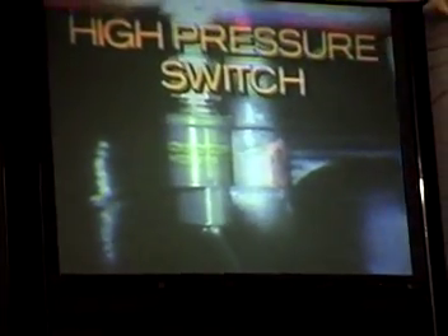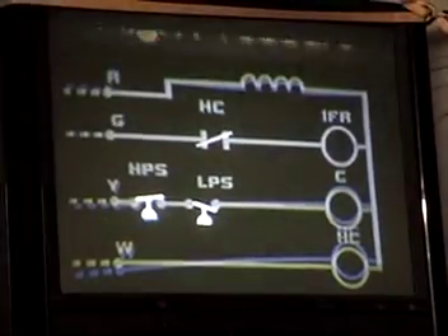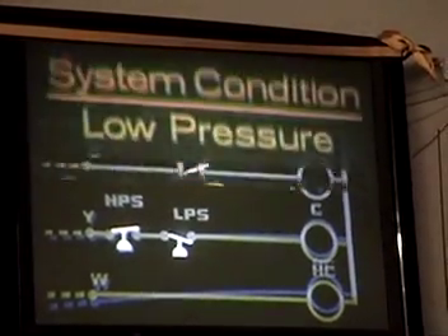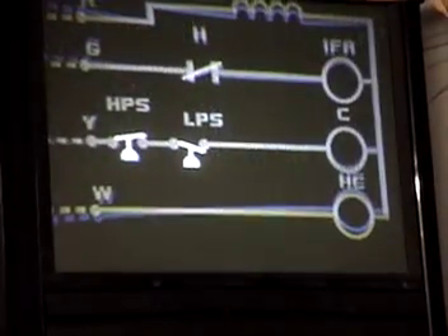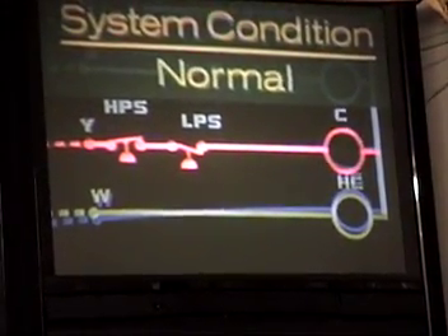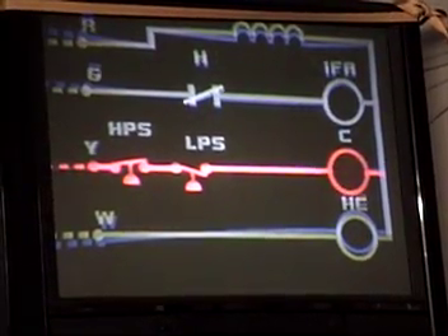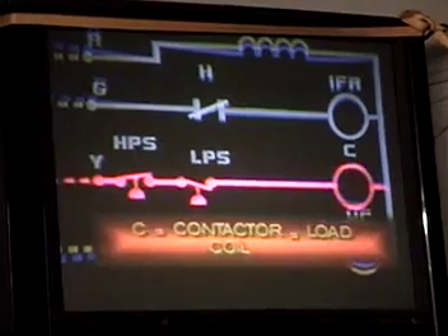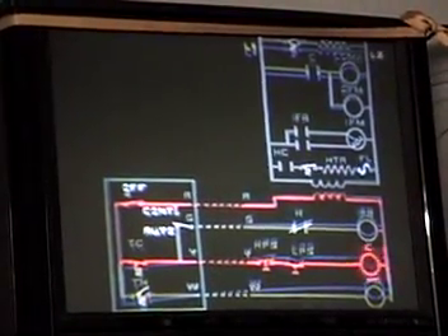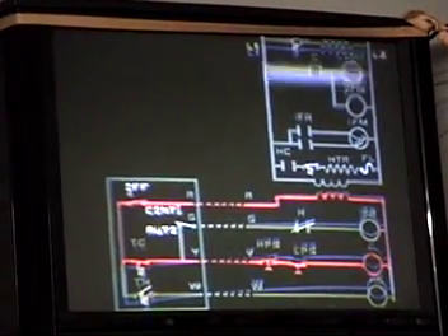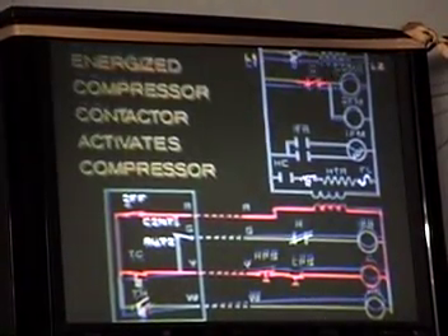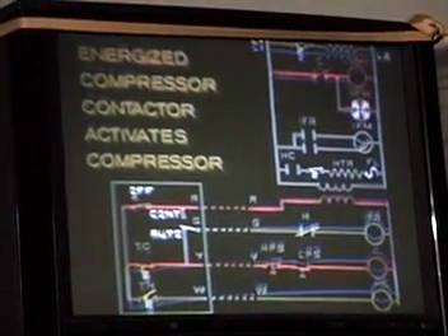The high pressure switch protects against excessive refrigerant system pressure, which could place a strain on the compressor and system. High pressures will open the switch and break the path to the compressor contactor coil. The low pressure switch protects against excessively low refrigerant pressure in the system, which could damage the compressor. If the system pressures are normal, both pressure switches will be closed and provide a continuous electrical path to the electrical load in the circuit. In this case, the load is C, the contactor coil. The contactor is an electrical coil which, when energized, closes the contacts ahead of the compressor and activates the compressor and the outdoor fan motor.